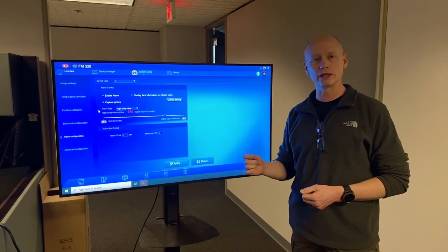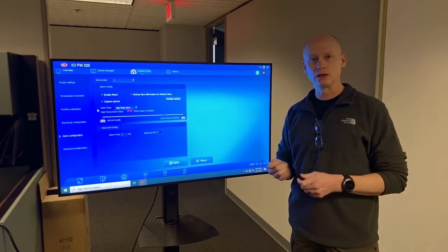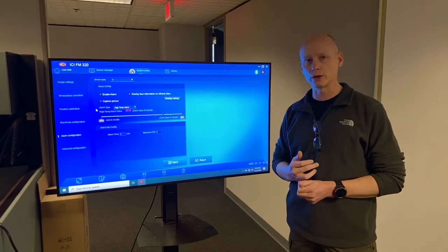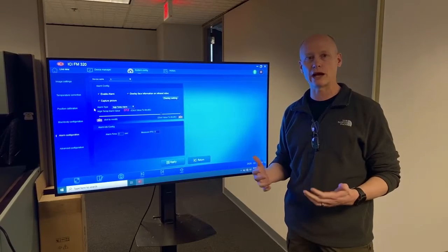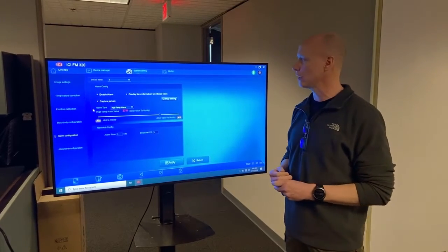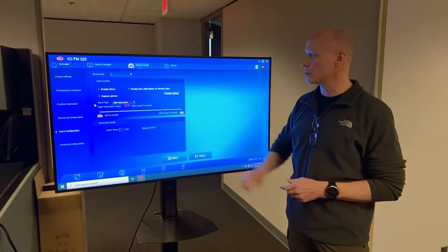There is a red and green alarm light. We're going to go over that. Couple things to keep in mind. You got people, there's a general population of males more susceptible that are red-green colorblind. We highly recommend having the audio alert. It's just a very subtle tone that comes up and alerts the operator, but we highly, strongly encourage to make sure that is always left on. So we'll enable the alarm, overlay face information.